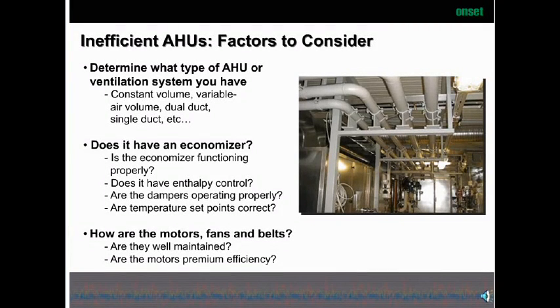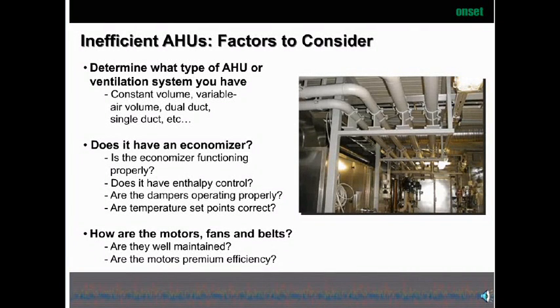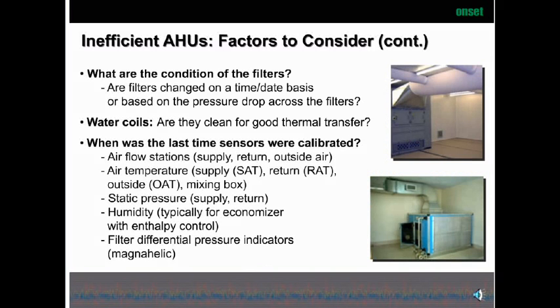Do your economizers have enthalpy control, and is that working correctly based on humidity and the temperature of the outside air? Are your dampers operating properly? Very often we find dampers not functioning properly — they are binding. People have put two-by-fours or other things to try to correct the problem and then forget about it, and years later you find these things still operating that way. Also look at temperature setpoints — are they correct? Sometimes people make adjustments because somebody's cold or hot, and then forget about it. And some even more basic things: are your fans and motors well-maintained? Do you have premium efficient motors?